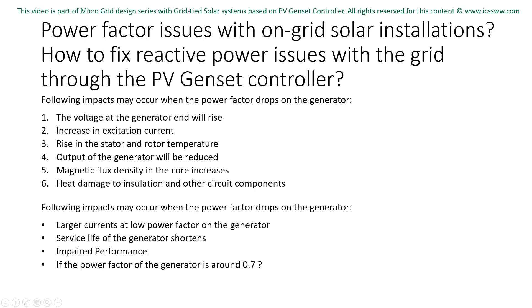The following impacts may occur when the power factor drops on the generator: the voltage at the generator end will rise, increase in excitation current, rise in stator and rotor temperature, output of the generator will be reduced, magnetic flux density in the core increases, and heat damage to insulation and other circuit components. Larger currents at low power factor mean the generator will have to work harder to produce less power. Due to these negative impacts, the service life of the generator shortens and performance is impaired.